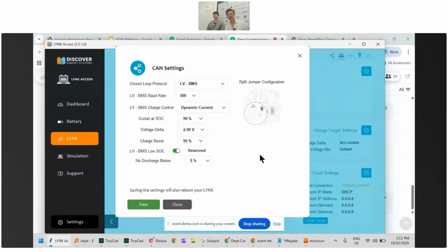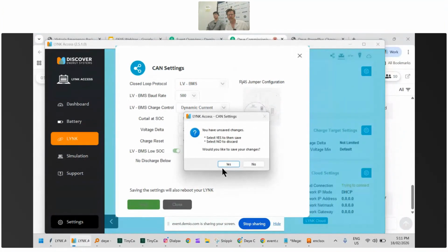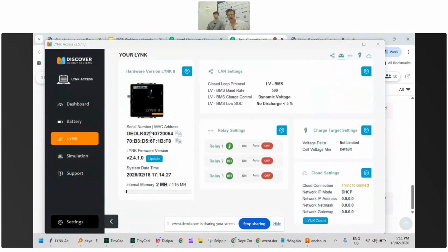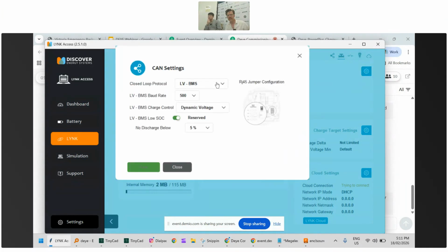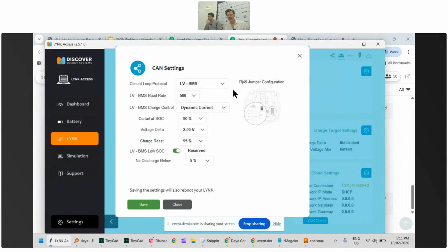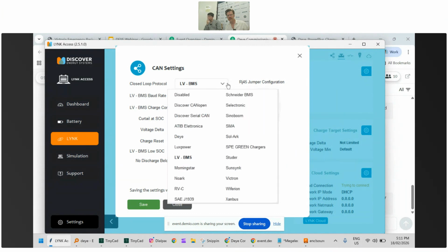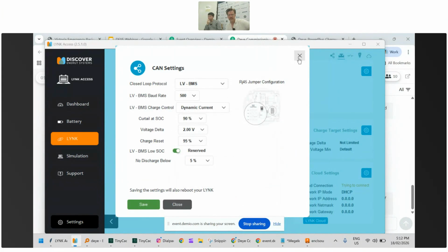Okay, here we are, so I'll just take you through that again. This will be very similar on the Helios - there'll be a CAN bus menu that looks a lot like this. You just click on the settings, and on a Helios it will come standard as dynamic voltage, and you just want to change it to dynamic current if you're using a Deye or a Noark. If you're using a LYNK II, then there are other options here like Deye, but we recommend actually using just the LV BMS dynamic current rather than the specific Deye one at the moment, because it's the more up-to-date one. It's not necessarily a fault of Discover or of Deye - I think it's just different styles of charge control, and then just optimizing those.